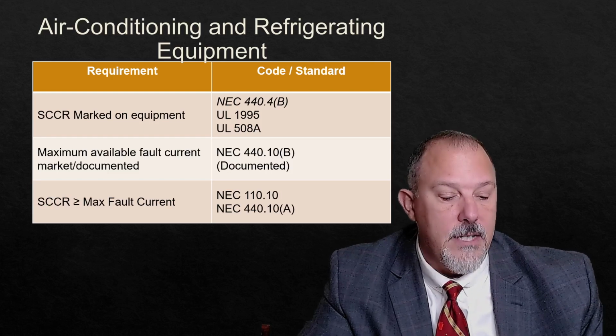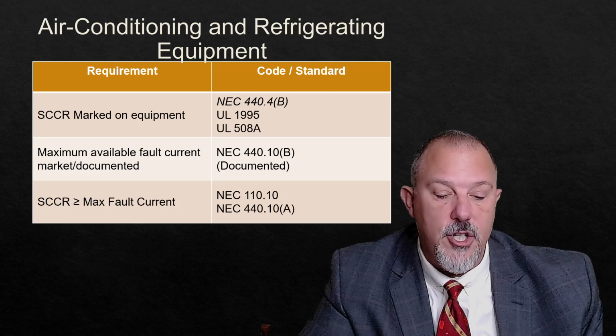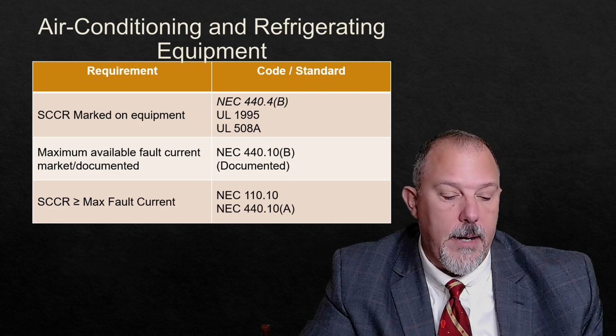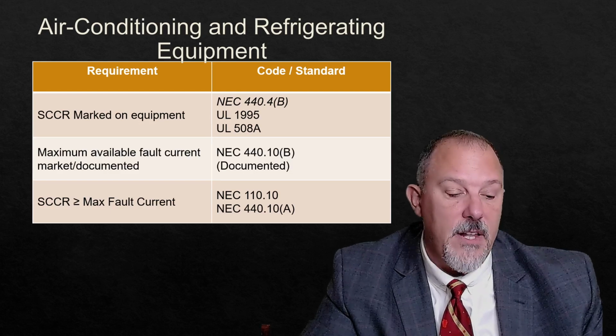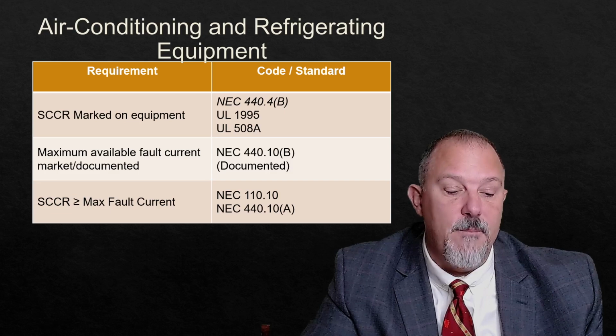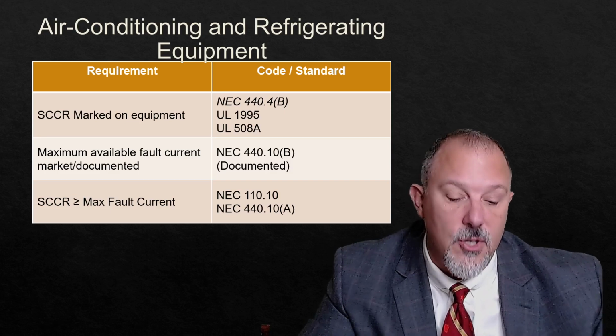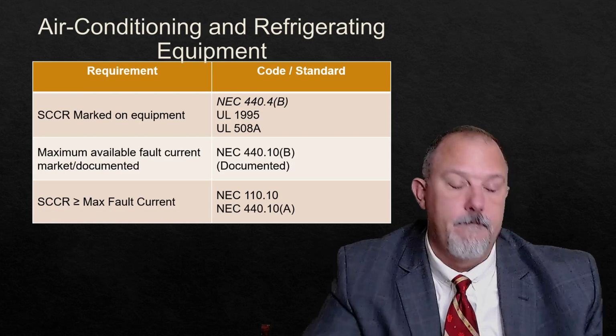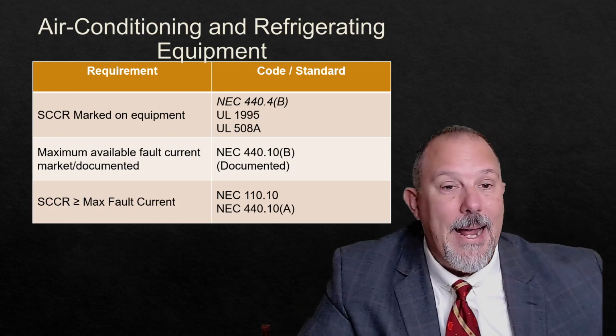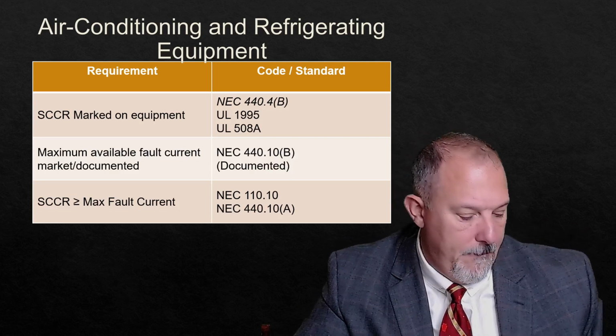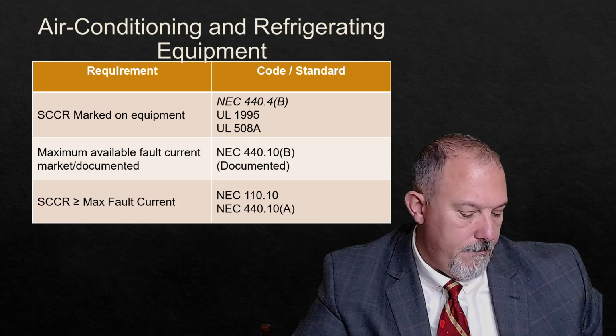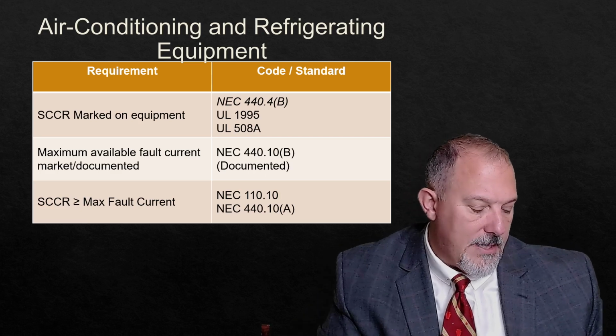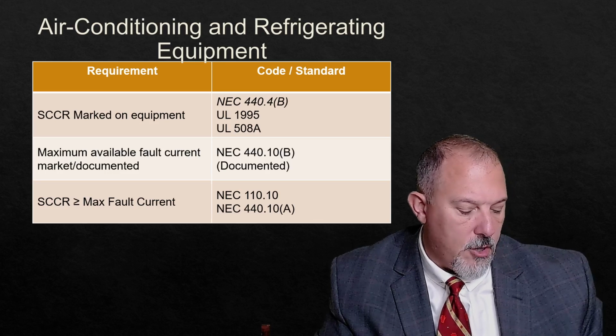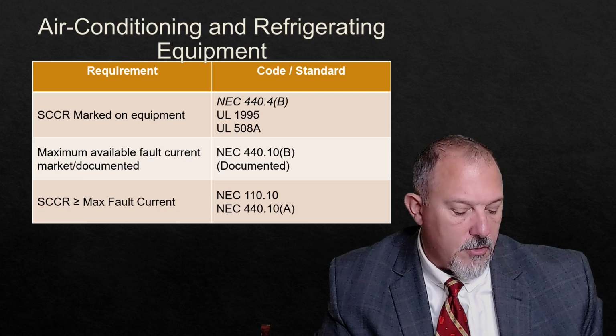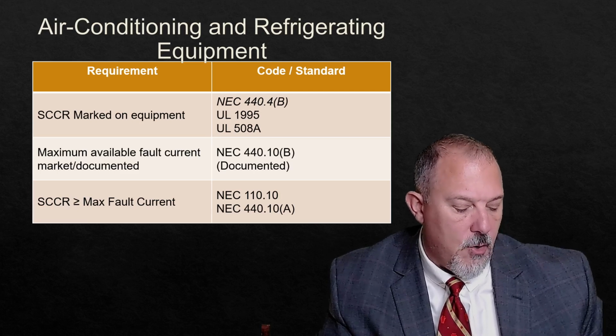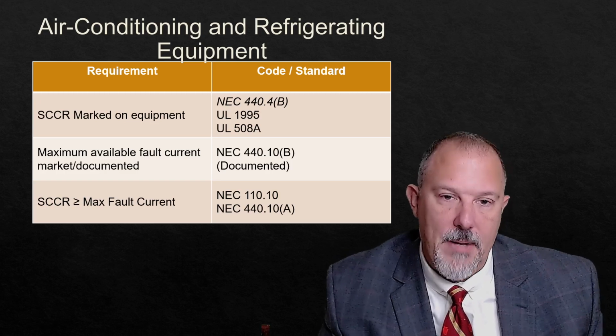When motor controllers or industrial control panels of multimotor and combination load equipment are required to be marked with a short circuit current rating, the available fault current and the date the available fault current calculation was performed shall be documented and made available to those authorized to inspect, install, or maintain the installation. Love this stuff. And based on 110.10 and 440.10A, which I just read. No, I didn't. 440.10A says motor controllers or industrial control panels or multimotor and combination load equipment shall not be installed where the available fault current exceeds its short circuit current rating as marked in accordance with 440.4B. It's a case.